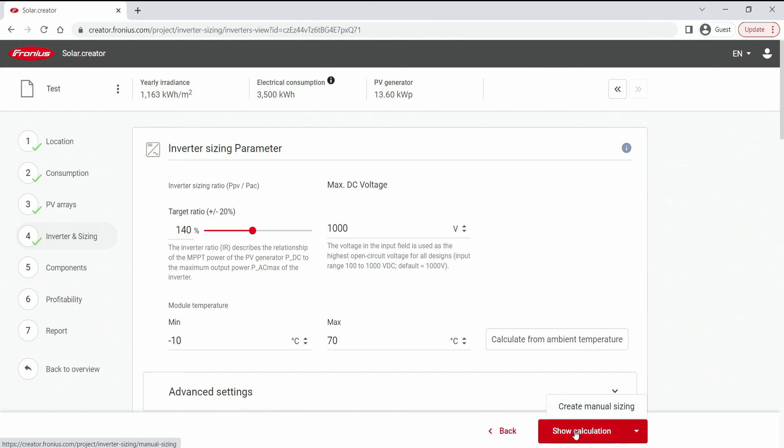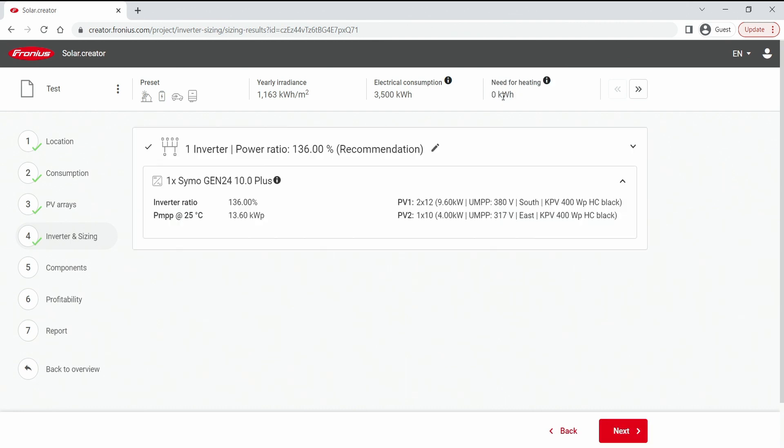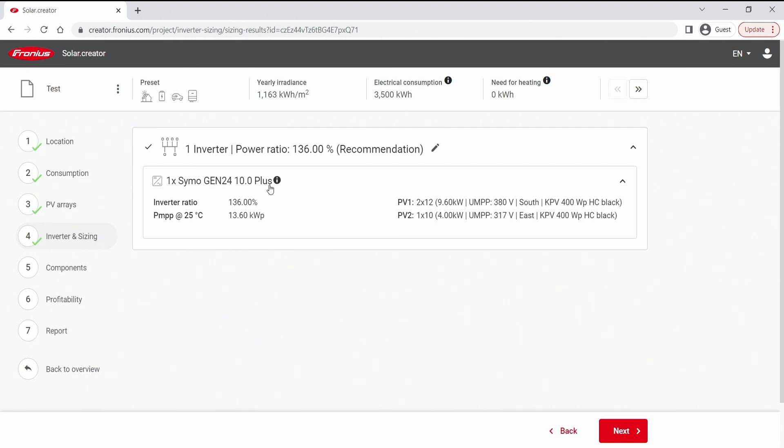So based on my input it will give me now a suitable inverter for my 13.6 kW peak generator size. And here it is with a ratio of 136 percent. So that's perfectly near my 140 that we have targeted. And it is no surprise the Symo GEN24 10 kW inverter. And it's even a plus inverter therefore we can add the battery.